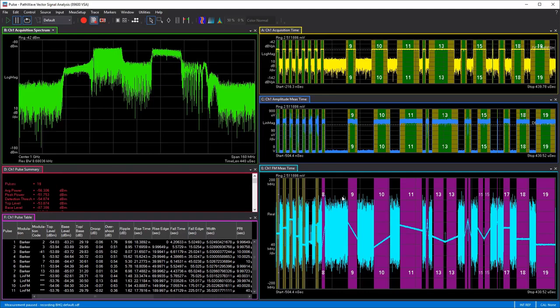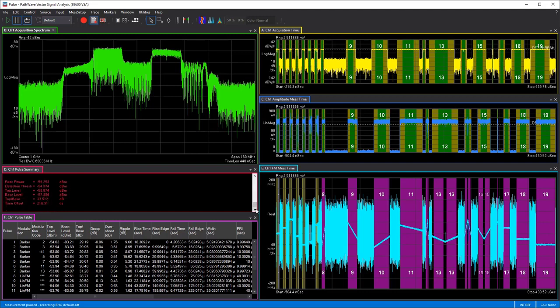A lot of the power of this particular measurement option is in the pulse summary and the pulse table. In the pulse summary you can see it displays the number of pulses captured — 19 — which correlates with the pulses in the acquisition time and the other traces, as well as things like average power, peak power, detection threshold, and so on — really high-level characteristics of the overall measurement.